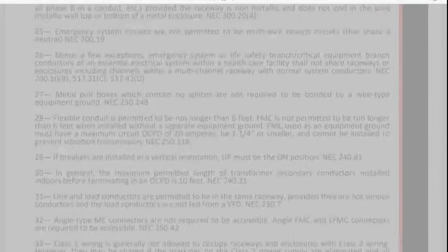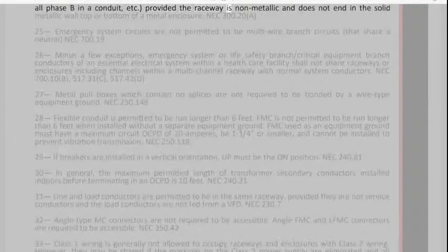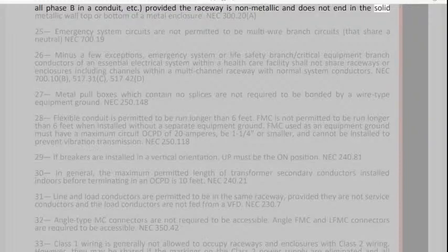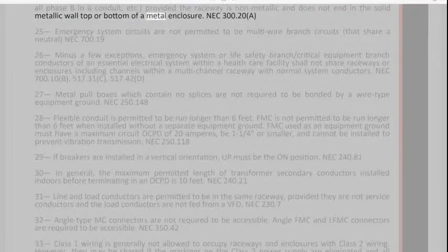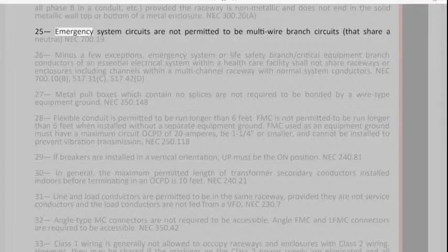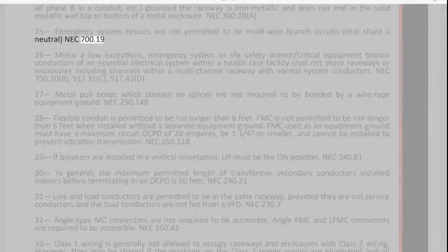24. Parallel feeds are permitted to be installed in an isolated phase manner, all phase A in a conduit, all phase B in a conduit, etc., provided the raceway is non-metallic and does not end in the solid metallic wall, top or bottom of a metal enclosure. NEC 300.20A. 25. Emergency system circuits are not permitted to be multi-wire branch circuits that share a neutral. NEC 700.19.